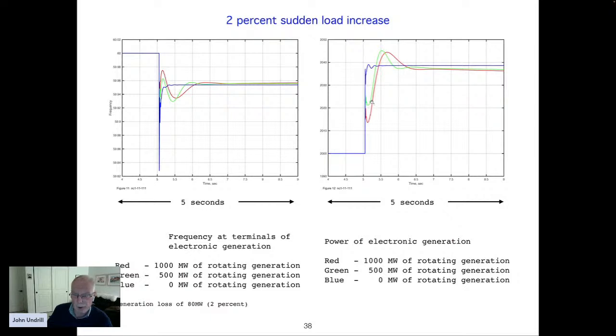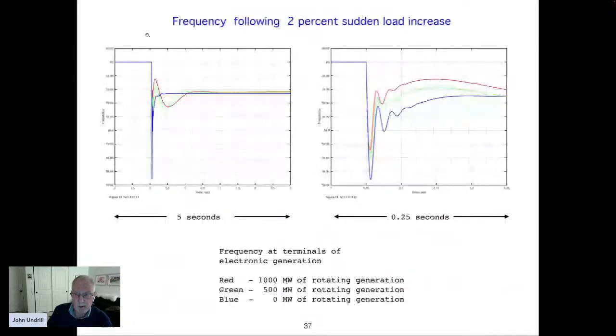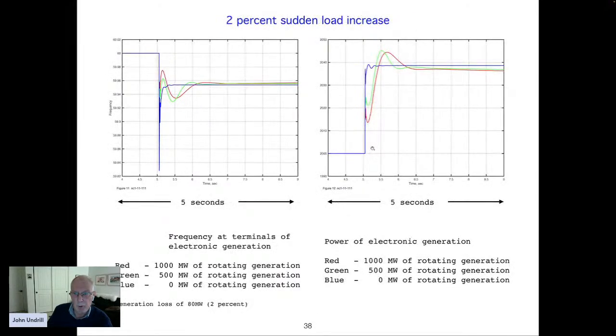As you decrease the amount of rotating generation, and decrease the inertia of the system, you both change the nadir of the frequency dip, which we saw on the previous slide. As you decrease the amount of rotating generation, you increase the depth of the frequency dip, and you require the electronic generation to maneuver a bit more. When it's all electronic, of course, the electronic generation has to do all the work, and it does it in a fraction of a second.